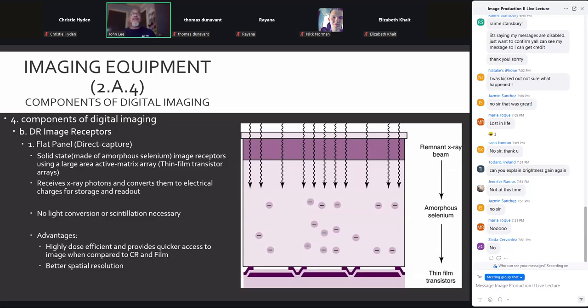Our DR image receptors, this one talks about the direct capture. Okay, we do have the indirect capture. It was described a few slides back in fluoro. Make sure you understand that we've got both of them in the digital imaging flat panels. Now, the difference between direct capture and indirect capture, where in indirect capture, we're getting the image after we convert the X-rays to light. In a direct capture system, we're actually utilizing the X-rays that come out of the patient to generate our image. There is no conversion to light. Okay, that requires a different detector element. Indirect capture uses amorphous silicon.